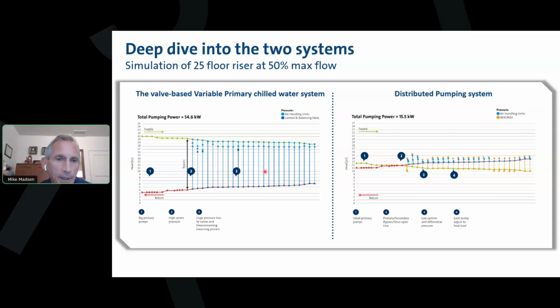What we've got is a building laying on its side. So this is floor 1 through 25. And so I can see with the variable primary, I'm producing a lot of head on that pump skid, and I'm sending a lot of head pressure out to that 25th floor.